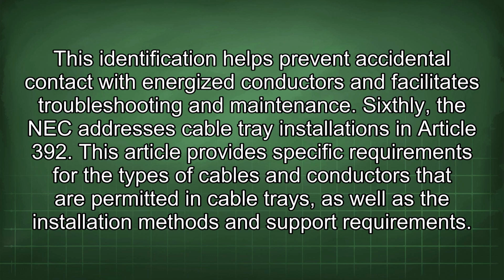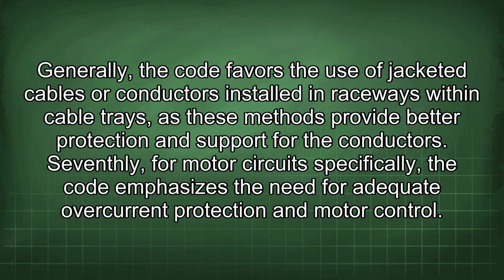Sixthly, the NEC addresses cable tray installations in Article 392. This article provides specific requirements for the types of cables and conductors that are permitted in cable trays, as well as the installation methods and support requirements. Generally, the code favors the use of jacketed cables or conductors installed in raceways within cable trays, as these methods provide better protection and support for the conductors.